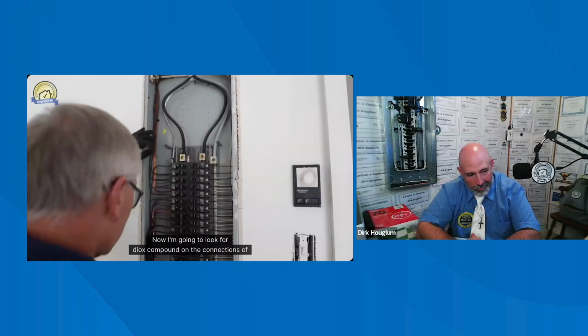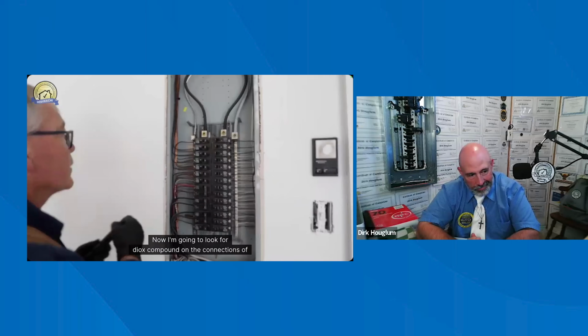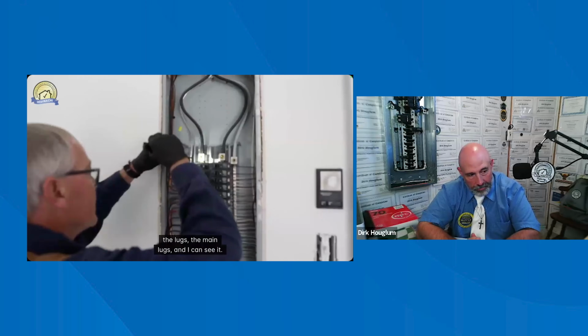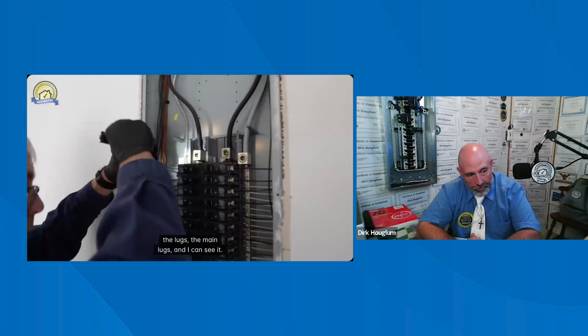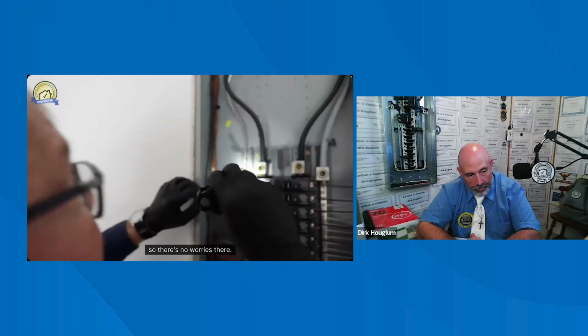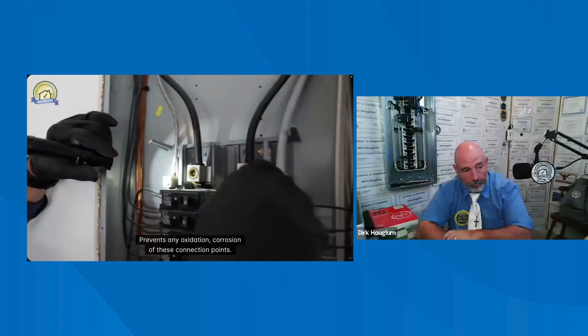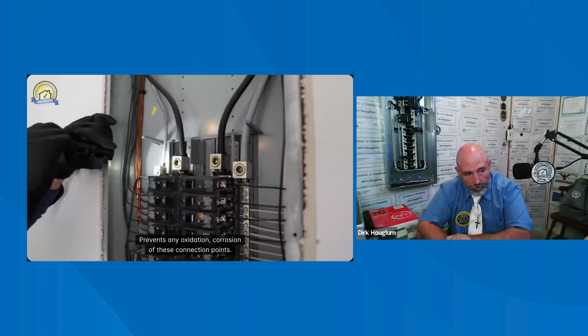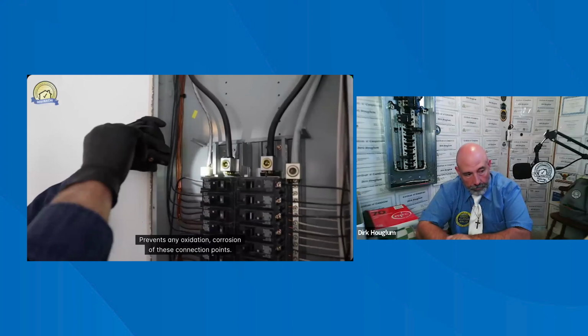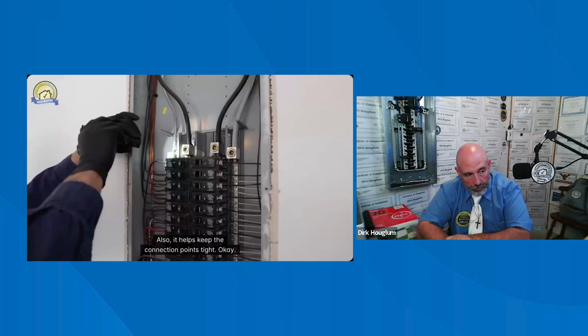Now I'm going to look for deox compound on the connections of the lugs, the main lugs, and I can see it. They've all been coated well, so there's no worries there. You see the paste up here? That's our deoxidizing compound. It prevents any oxidation or corrosion of these connection points. It also helps keep the connection points tight.